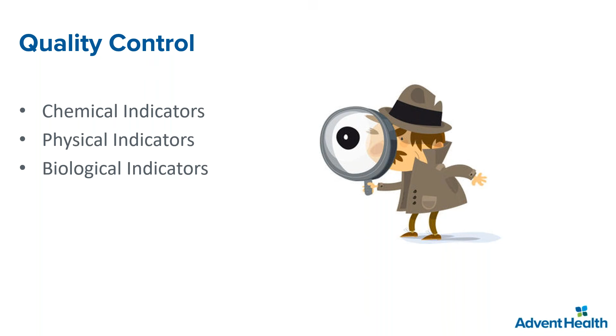We run quality control for all the trays and all the instruments that go inside a sterilizer. We have what is called chemical indicators, physical indicators, and biological indicators. Chemical indicators are designed to show a visible color change when the device has been exposed to the sterilization process. For instance, we have steam indicators that change from white to black. As an example, if you see this tape here, this is the steam indicator, because those stripes are white, and when it goes through the sterilizer and they apply heat, it's going to change to black.